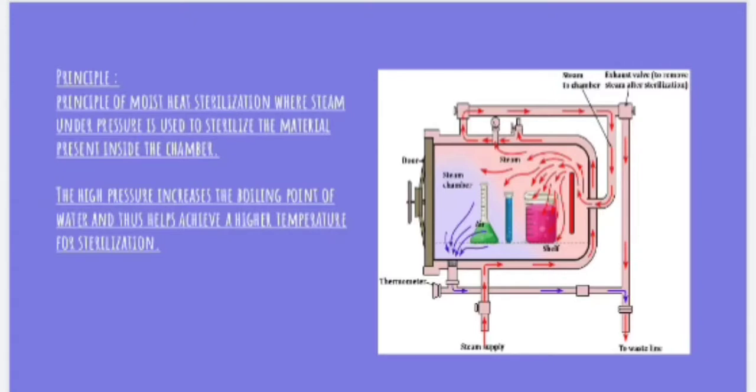The safety valves are adjusted to maintain the required pressure in the chamber. Once the water inside the chamber boils, the air water mixture is allowed to escape through the discharge tube to let all the air inside to be displaced. The complete displacement can be ensured once the water bubbles cease to come out from the pipe.